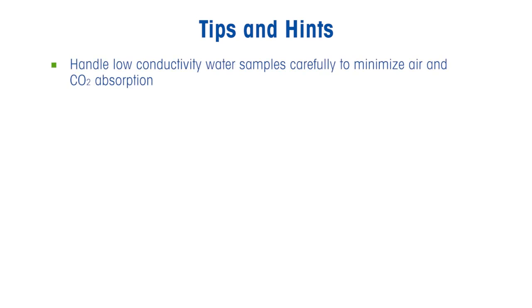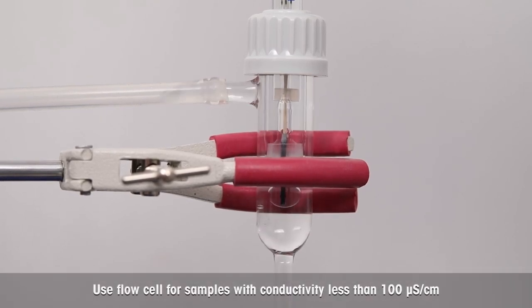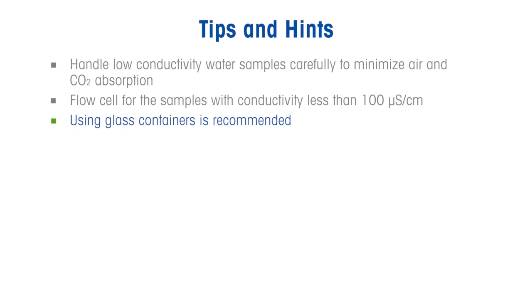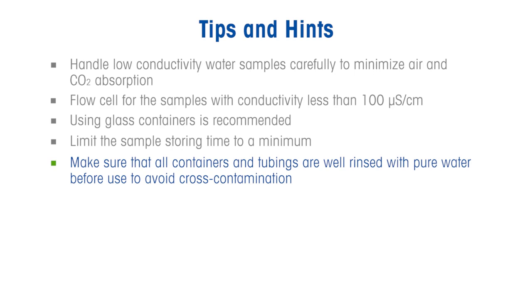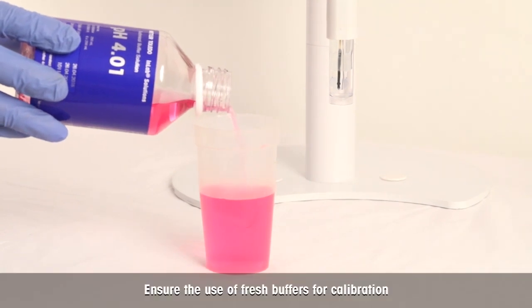Some tips to get accurate and precise results. Take maximum care to avoid any exposure to air and atmospheric carbon dioxide, even during sample handling. If possible, measure the sample directly from the source. Use a flow cell for the water samples which have conductivity less than 100 microsiemens per centimeter. Using glass containers is recommended, since air can diffuse through plastic. Test the samples as soon as possible after collection to minimize temperature changes, sample aeration, and contact time with the sample container. Make sure that all containers and tubings are well rinsed with pure water before use to avoid cross-contamination. Always use fresh buffers for the electrode calibration.